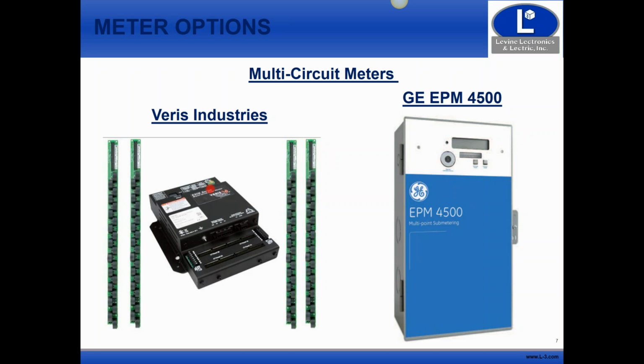So what we like to see from a cost standpoint for the owner, to fulfill this requirement and keep the cost down, is to try to separate the loads as much as possible beforehand, rather than separating them out at a monitoring level. So that's what we like to see. We're not always able to do that. I have seen several times where the engineer did it on all of them but one, because that one panel, like I said, was out far away. It just wasn't practical to do it that way.